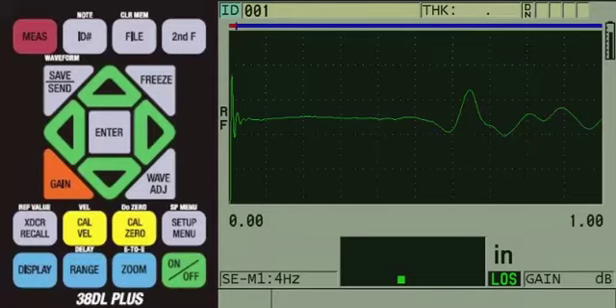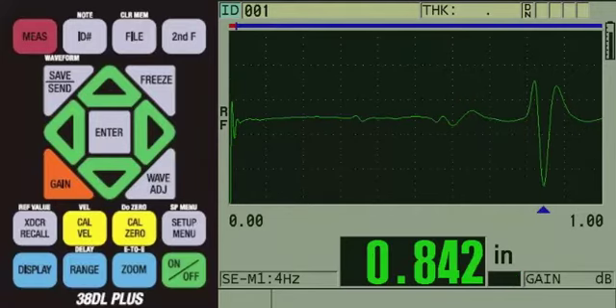Now, since we changed the velocity to be close to rubber and we adjusted our range appropriately, we have a rough idea of where the back wall echo should appear. Given the thickness of the part, the total thickness back wall echo should appear to the right of the center of the screen when using imperial units. If you are using metric units, the total thickness back wall echo would appear towards the middle of the screen. We can now apply couplant to the part and couple the transducer onto the sample in a spot between the steel cords. We start to get a reading which looks to be correct.